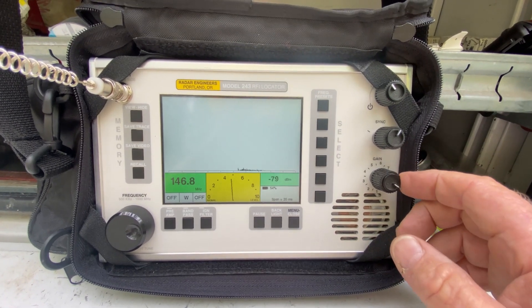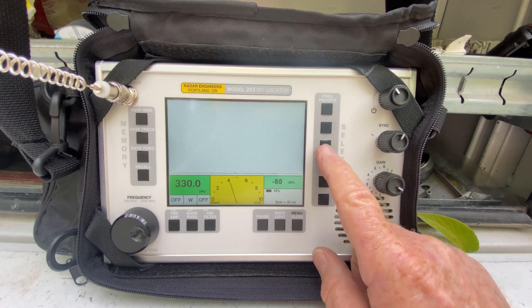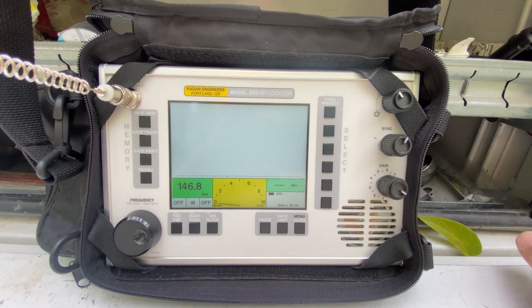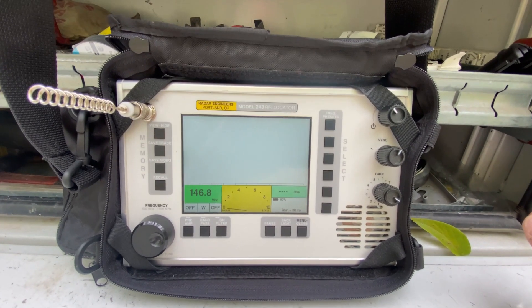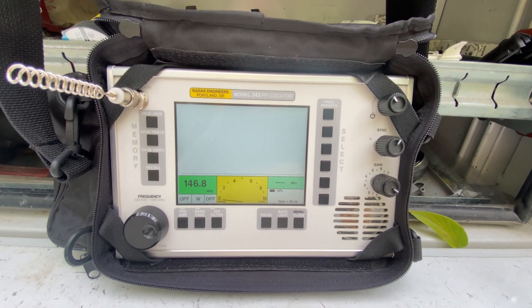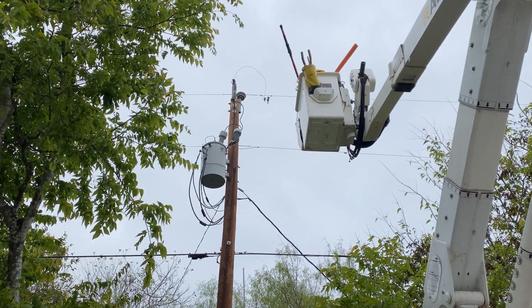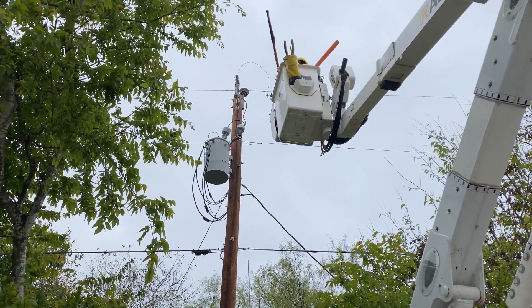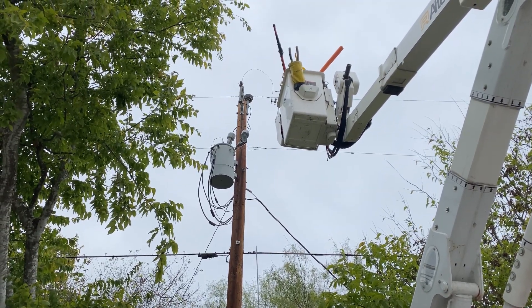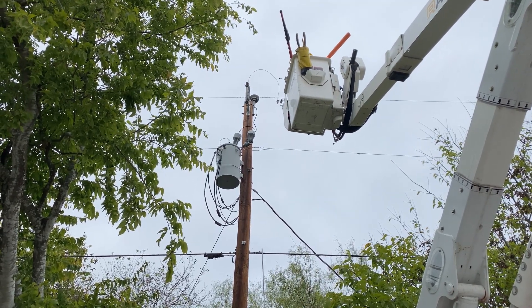So we're at full gain, 330, then 146.8 on full gain. With this antenna I'm close enough to the pole that it shouldn't make any difference. We were able to isolate this RFI issue. He brought the transformer energized and now he's going to check for noise with the transformer and the new arrestor hot.